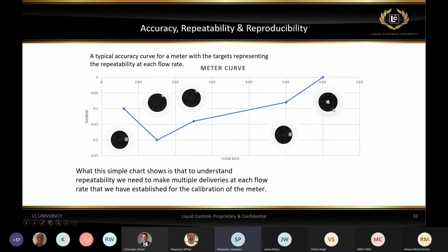So it's a little bit larger meter, and there's a target representing repeatability of that meter at that flow rate. Again, if you look at the overall curve, you're going to see a few things here. First of all, if you look at each point, the meter is repeatable at every point. You see the clusters of the points, they're close together, so the meter is repeatable. That's definitely what we're looking for.